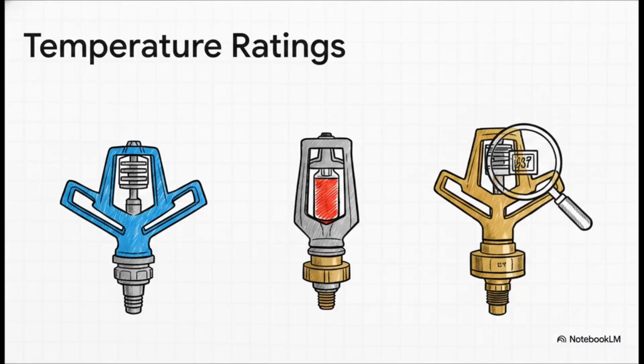Now you might be wondering, how do we make sure a sprinkler directly above a blazing industrial oven doesn't go off normally, while one in a heavily air-conditioned office triggers immediately? It's all about temperature ratings. Engineers give these fixed spray nozzles highly specific temperature tolerances, and you can identify them visually in 3 really clever ways. The sprinkler frame arms might be color-coded, the liquid inside that glass frangible bulb will be a very specific color, or, plain and simple, the exact temperature rating is physically stamped right into the metal of the sprinkler itself.